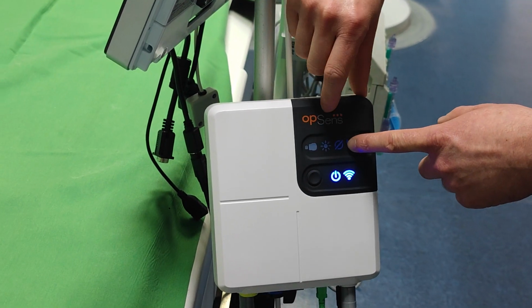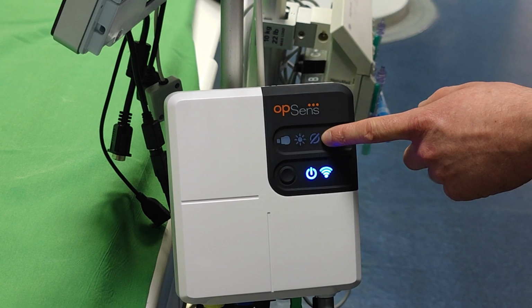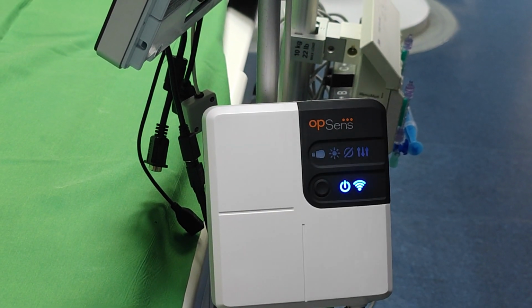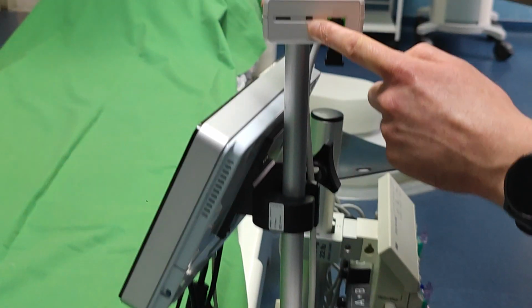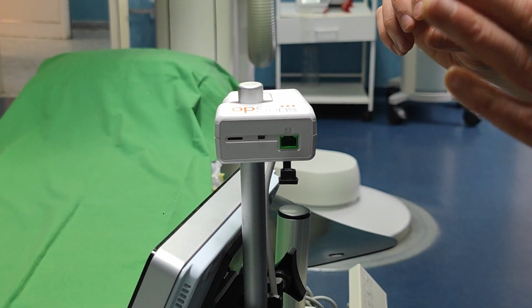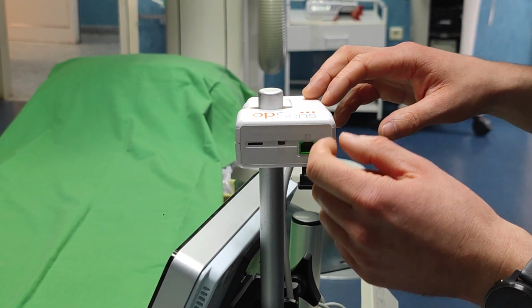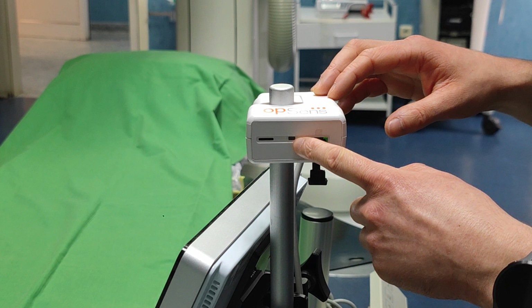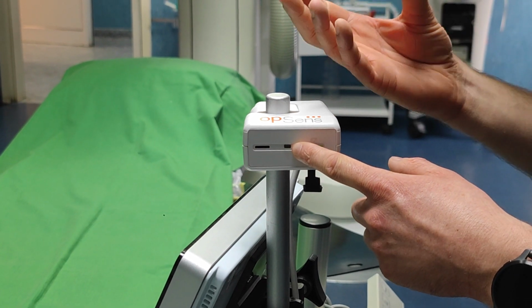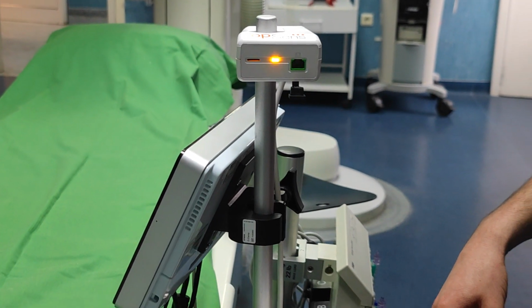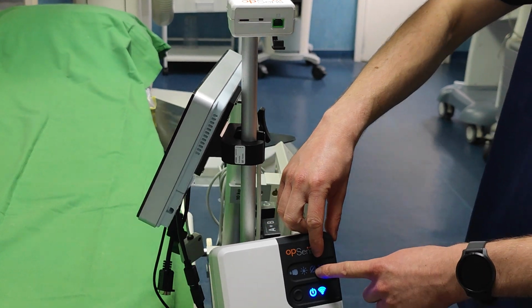This is the 0, so this means it's been properly zeroed. The other way to check for that, on the handle unit itself, you can see there's a yellow light. That's because there's just a single blink. That's because nothing's connected. When you connect your wire in, this will turn green. You'll get a nice audible beep. And this should also come on to say it's been zeroed successfully.